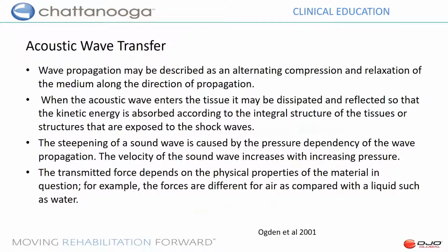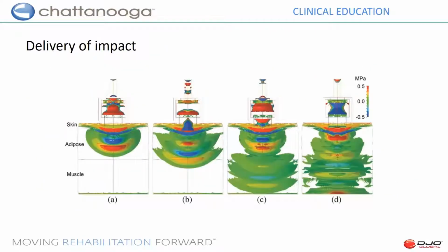And we do that repeated times over. So the wave will repeat and propagate, and that's actually what enhances the amount of energy that's delivered to the tissue, as well as that wave propagation that gives us the ability to get to a depth of upwards of 6 centimeters with radial pressure wave, and with focused shock wave, we can actually get as deep a therapeutic value of about 13 centimeters. So really some capability of delivering high amounts of mechanical energy into tissues that otherwise we can't do with other physical agents.